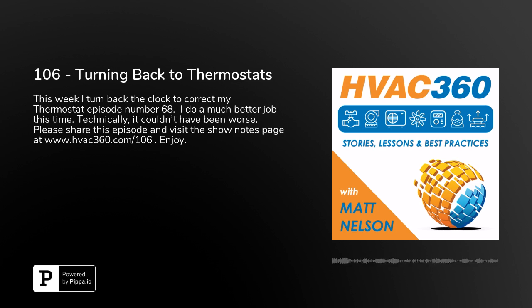A lot of times accuracy is not a huge deal in comfort HVAC, but it is something that you need to take into account, and also response time. Is it something that's going to be changing slowly, or is it going to be reacting fast? Generally speaking, when you're dealing with comfort, you're dealing with something that's changing slowly. The accuracy has to be relatively good, but it doesn't have to be totally precise. And the range just has to be in a good occupiable range, around 70 degrees Fahrenheit, plus or minus, say, 30 degrees. I think that would be reasonable. So those are some of the basic things you want to think about.